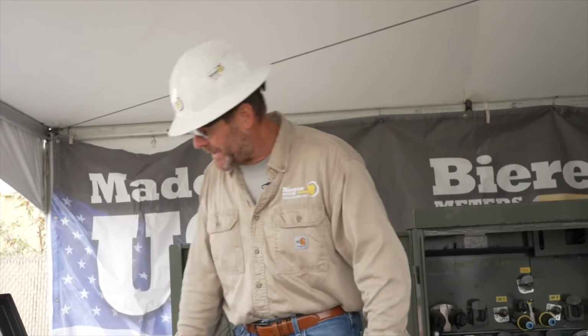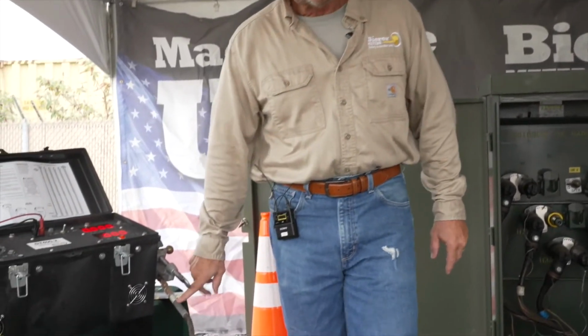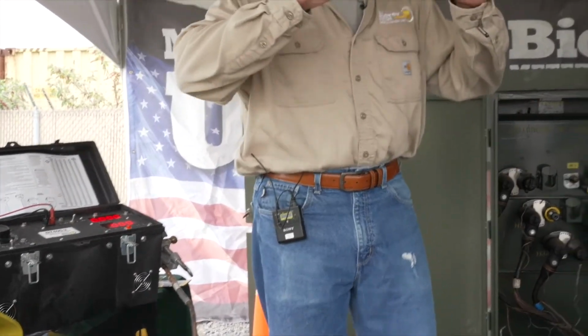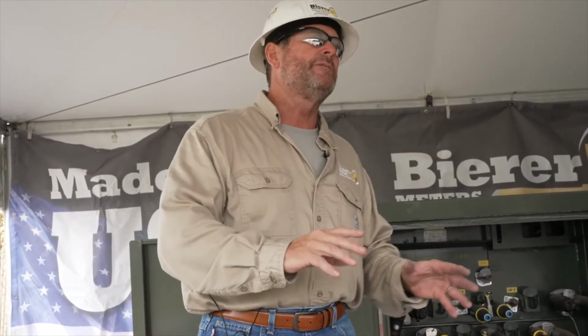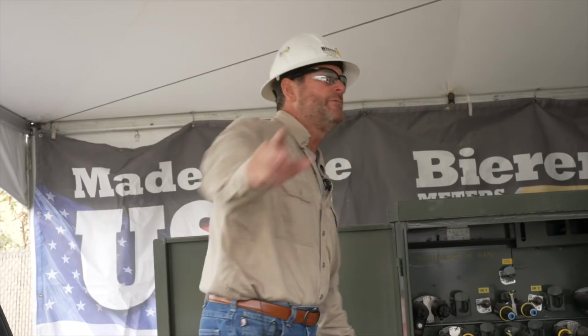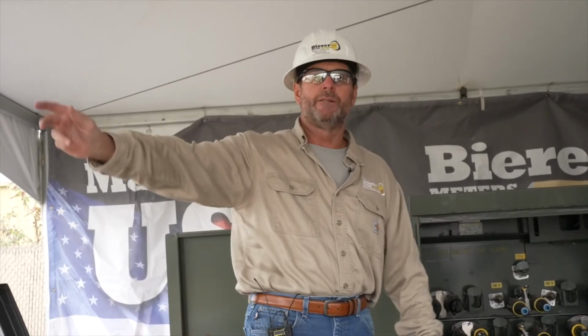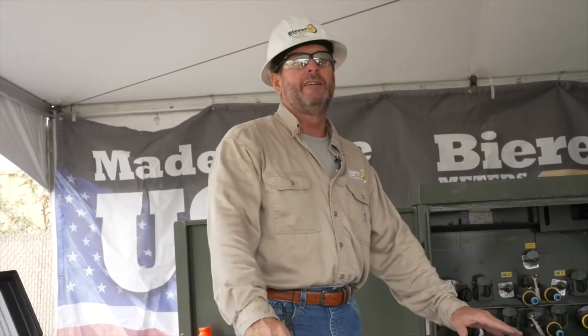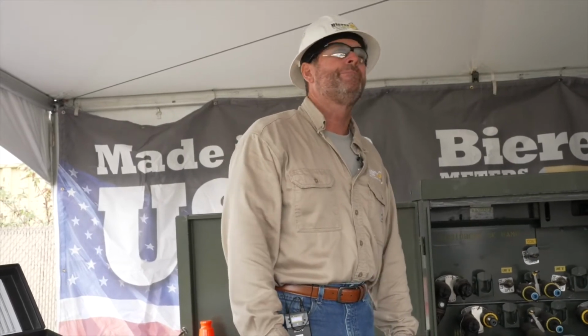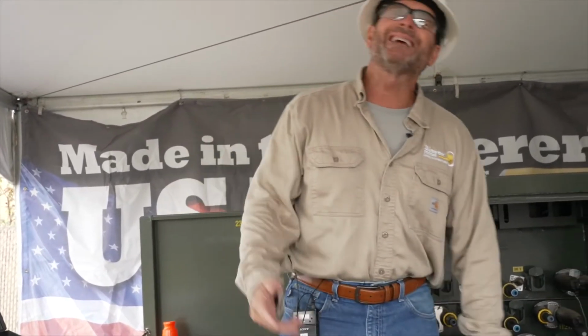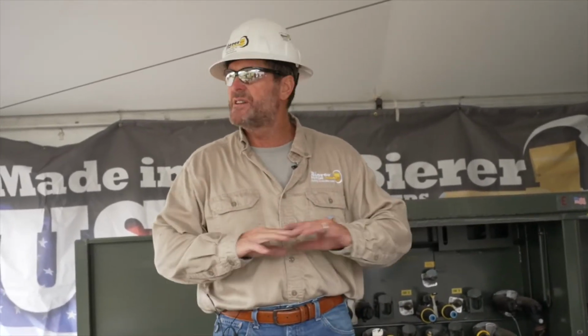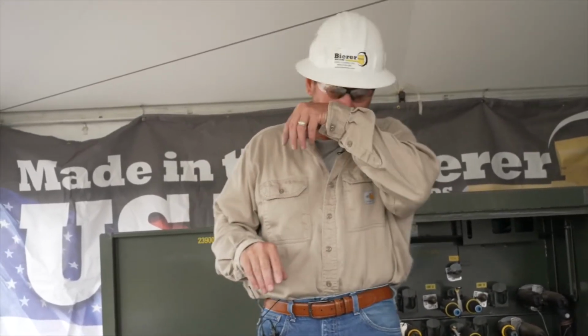You also want to verify that there is a date stamp on your assembly showing when it was last electrically tested. Believe it or not, there are still folks who, to my face, say they do not electrically test their TPGs. Fact. Unbelievable, that's crazy. But the guidelines say to test them, they just don't say how often. Makes zero sense to me.